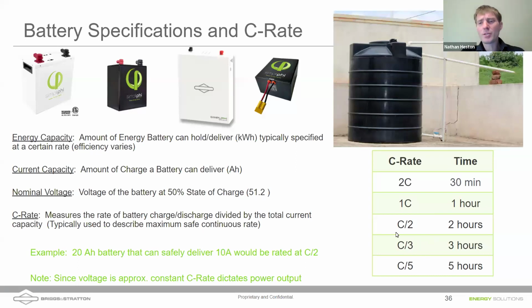Most of our competition is somewhere in the C/2 to C/3 range. Most people don't want to discharge their battery that quickly, but they would like to charge it quickly, especially if they have a generator — they want to run that generator the least amount of time. Keep in mind all of our batteries currently are rated at C/2. You wouldn't want to charge them faster than 2 hours, and the same applies to the discharge rate.